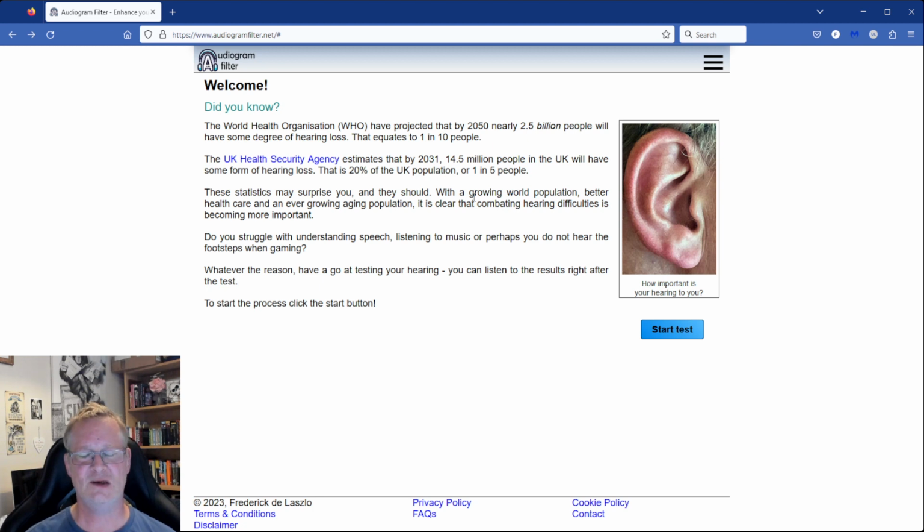And what I mean by this is that the average human auditory range starts at about 20 Hz, which is very, very low, think bass, up to 20 kilohertz or even higher, which is very, very high. And the hearing aids only go from about 125 Hz to 8 kilohertz because quite naturally it's based on speech. They want to be able to have a conversation. It doesn't really work for things like music or going to the cinema or on your device listening to music or watching some video and so forth.